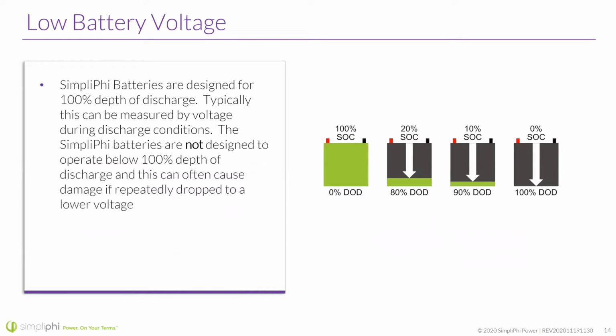I will say one thing about low battery voltage. There's a little bit more give there where the BMS will most likely disconnect. And if you screw up once or twice, it's probably not the end of the world. The battery just probably needs a charge and a reset. This is something that will cause damage more likely if repeat offense. You just continue to over discharge the battery over and over and over again. That's when oftentimes this will become more of an issue than the other, like over discharge or overcharge.